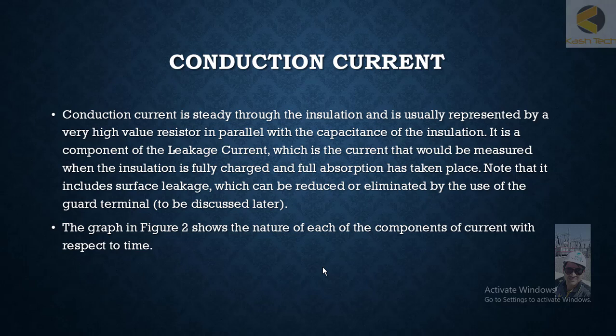Surface leakage should be subtracted from the calculations of the insulation resistance test. We use a guard terminal for this, which will also be discussed in detail. This is the basic conduction current for insulation measurement.